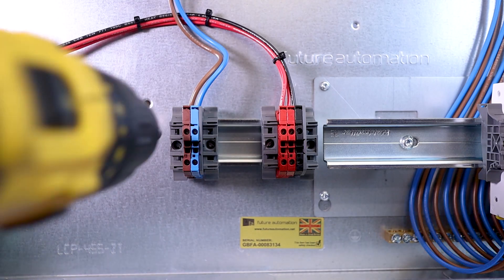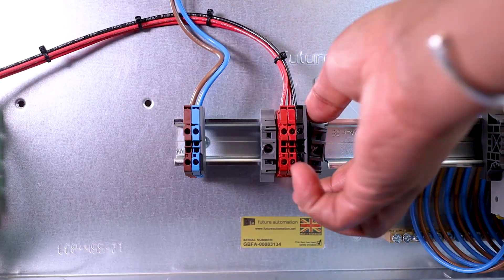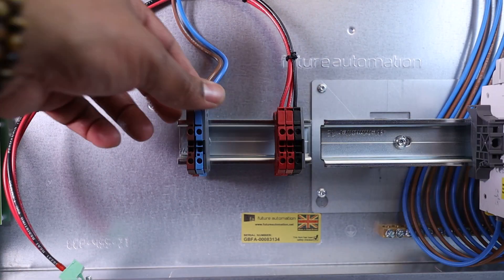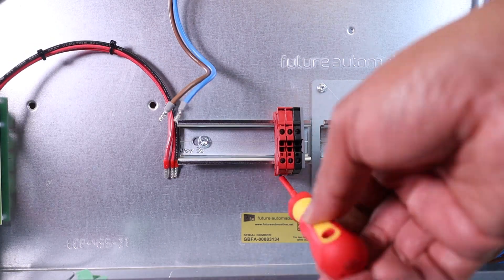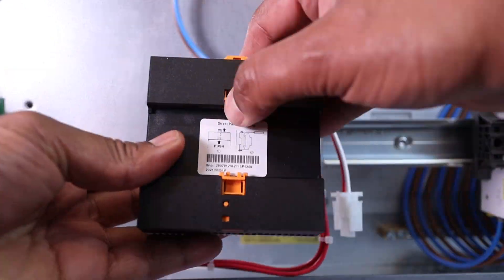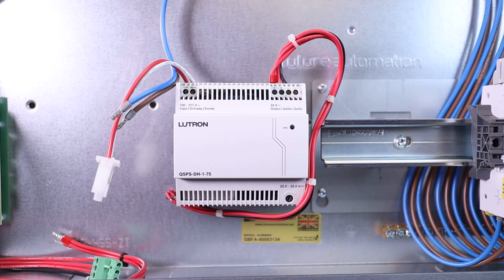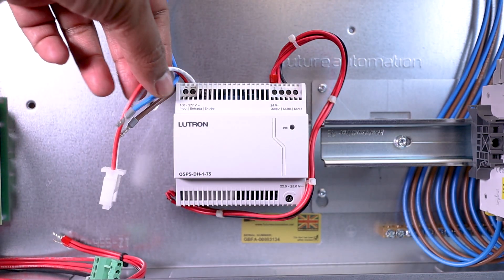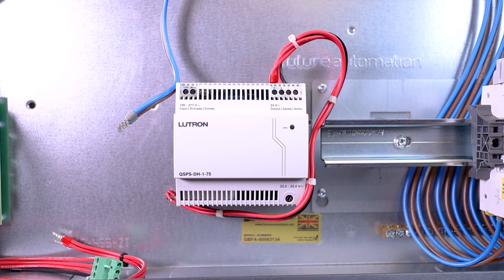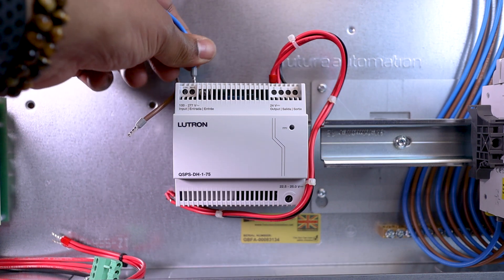Same thing here, I remove first the terminal end stops. I release the pre-wire cables to be able to remove the terminal connectors, so I can install the Lutron power supply. Okay, next, I remove the mains feed-in cable from the unit, as I'm going to use the panel's pre-wire cable coming from the breaker to feed the power supply.